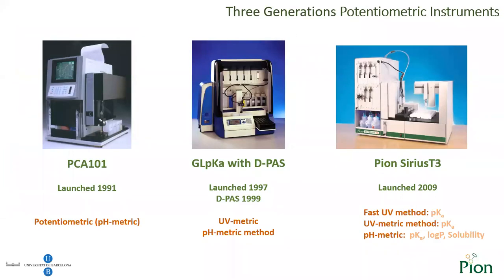In this slide, I would like to show you the three generations of potentiometric instruments for the determination of physicochemical properties designed by Pion, formerly Sirius. I worked with the PCA101 throughout my thesis, an automatic potentiometer which uses a pH-metric technique for the determination of pKa and log P. The GL-pKa with D-PAS introduced the UV-metric technique for pKa and potentiometric solubility. Our current system, Pion SiriusT3, reduces by a factor of 10 the amount of sample required compared to the GL-pKa, incorporating the same techniques plus the addition of Fast UV, which allows measuring pKas in just a few minutes at very low concentrations.